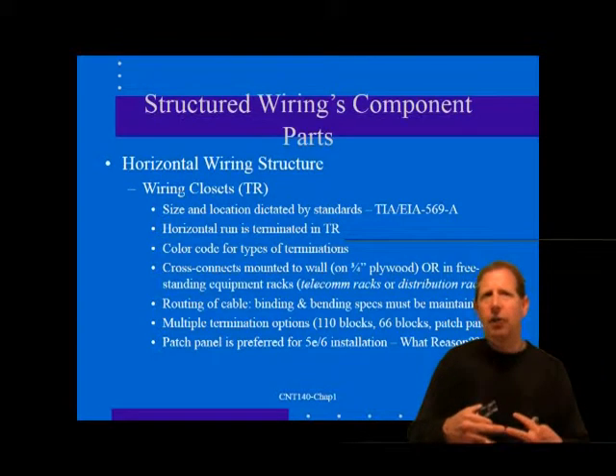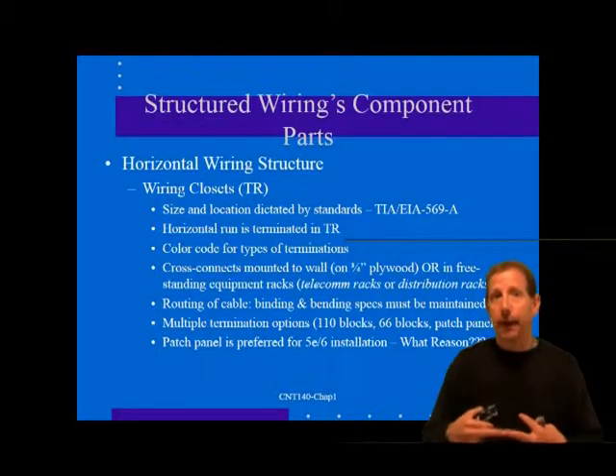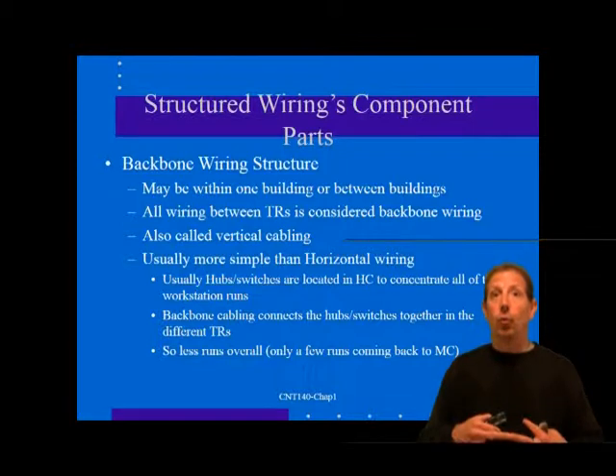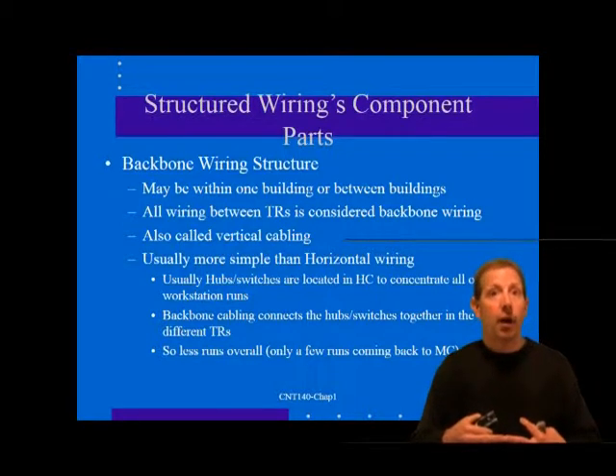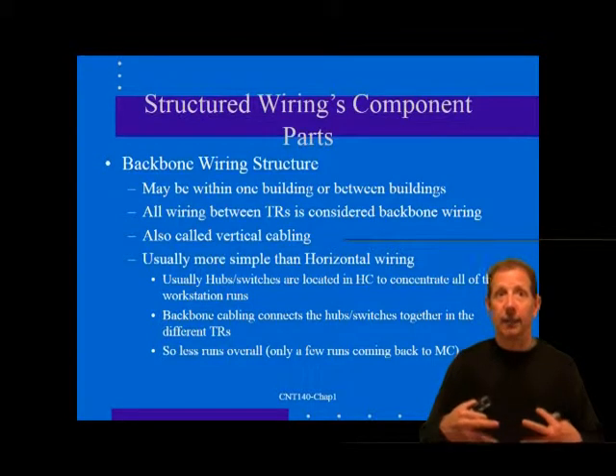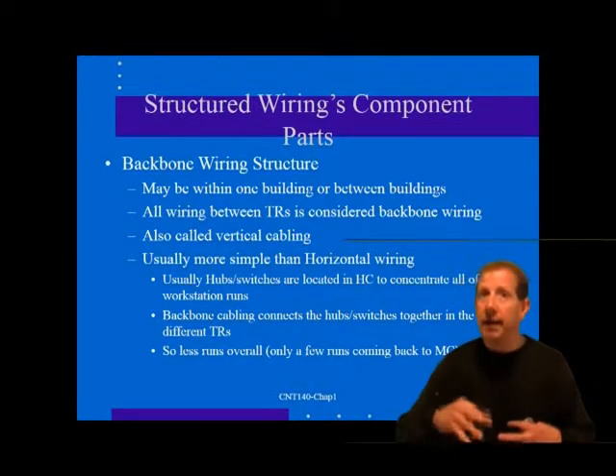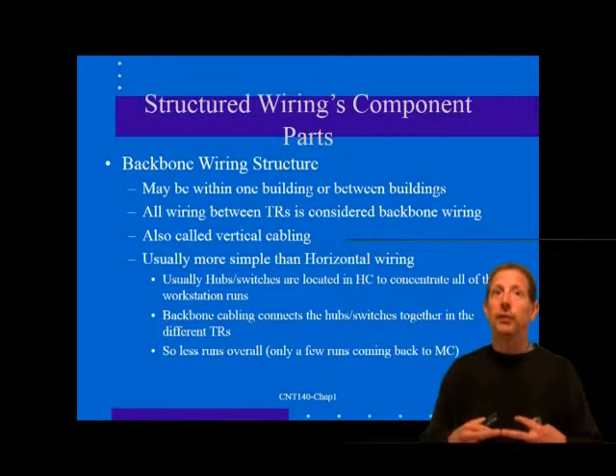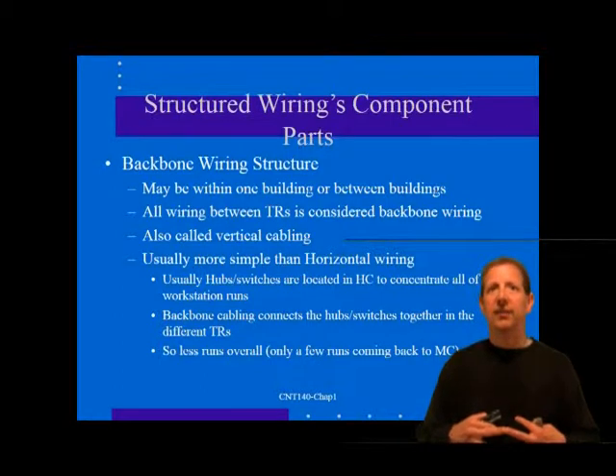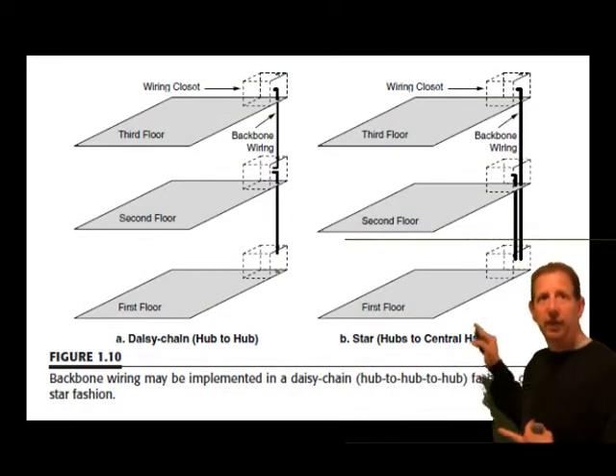Installation testing is simplified with patch panel termination because all station cables can be easily scanned to a certification standard. The only possible disadvantage is that multiple-use applications of the station cables are difficult, since each cable terminates into one patch panel location. Backbone wiring may be within one building or between buildings on a campus. All wiring between telecommunications rooms — MCs, ICs, and TRs — is referred to as backbone wiring. In many cases this backbone wiring will be between wiring closets on the same floor of a building.